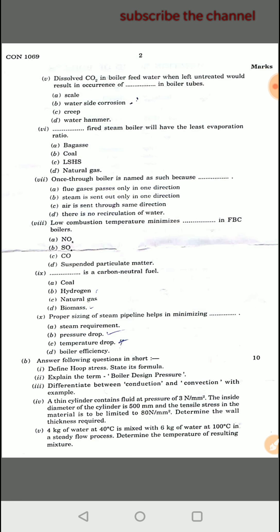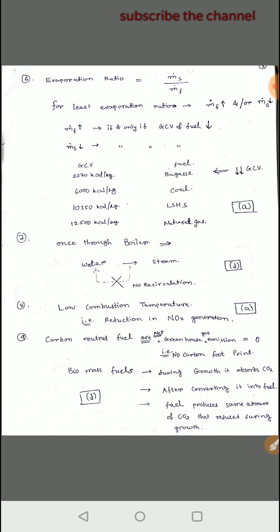D. There is no recirculation of water. It is a very simple question, and the answer is that once through boiler does not have water recirculation. Water is directly converting into steam. There is no recirculation from drum. There is no boiler drum in once through boiler.